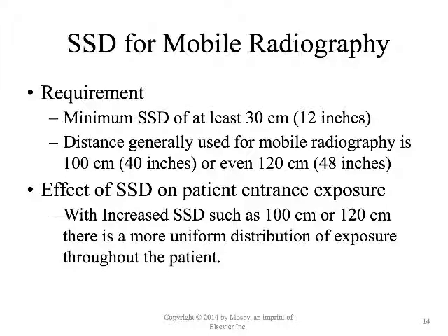SSD for Mobile Radiography. SSD stands for source to skin distance. There are requirements for these. A minimum SSD that can be used is 12 inches. If you're getting closer than 12 inches, something's not right.